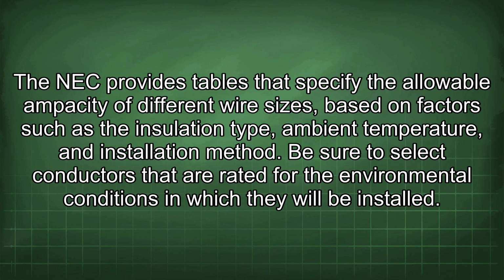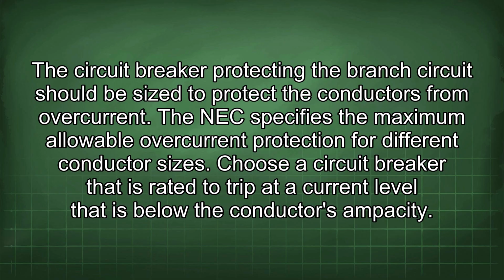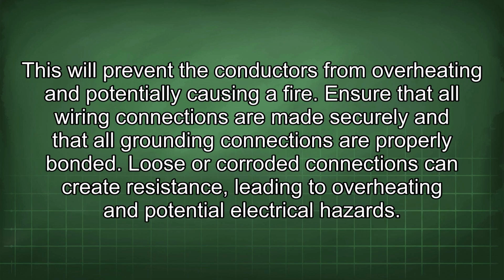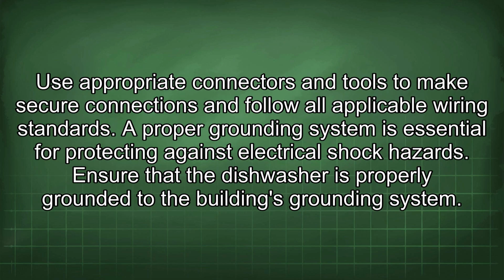Be sure to select conductors that are rated for the environmental conditions in which they will be installed. The circuit breaker protecting the branch circuit should be sized to protect the conductors from overcurrent. The NEC specifies the maximum allowable overcurrent protection for different conductor sizes. Choose a circuit breaker that is rated to trip at a current level that is below the conductor's ampacity. This will prevent the conductors from overheating and potentially causing a fire. Ensure that all wiring connections are made securely and that all grounding connections are properly bonded. Loose or corroded connections can create resistance, leading to overheating and potential electrical hazards. Use appropriate connectors and tools to make secure connections and follow all applicable wiring standards.